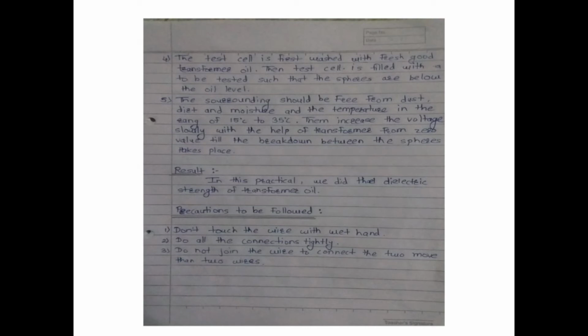Fifth, the surrounding should be free from dust, dirt and moisture, and the temperature in the range of 15 degrees Celsius to 35 degrees Celsius. Then increase the voltage value slowly with the help of the transformer from zero value till the breakdown between the spheres takes place. Result is that in this practical we determined the dielectric strength of transformer oil.